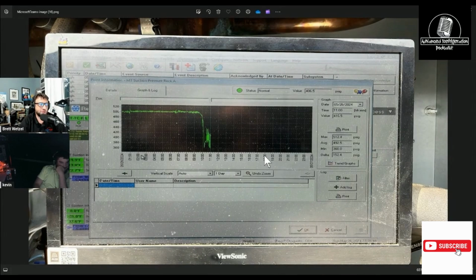And then I had him send me what the hot gas dump looked like. And then it was working for a little bit. And then you can see it just grenaded and then just went down. The other theory that I had was, like, why it ends up failing at 6 o'clock. Because then I had the liquid injection valve that hadn't been feeding at all. That wasn't feeding. And then the next thing I had him basically measure, put on the graph here on MT, was the discharge temperature of the low temp compressors. So my theory was it was trying to feed, and the only reason why it didn't fail and the superheat didn't go into the no zone is because your low temp compressors were still feeding, because you didn't have anything in defrost.